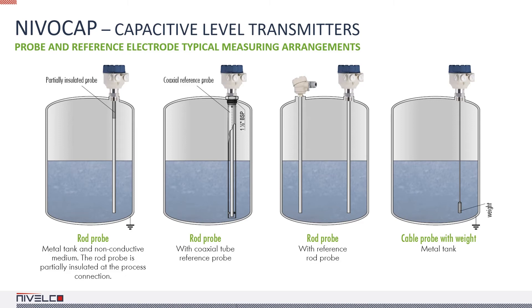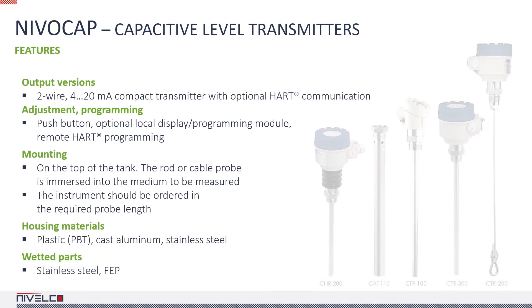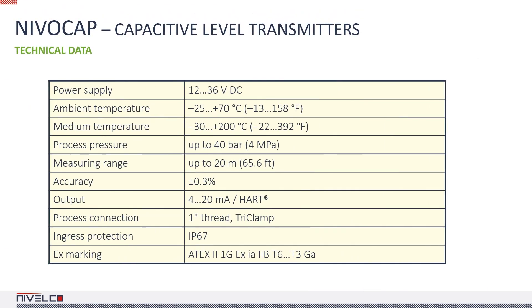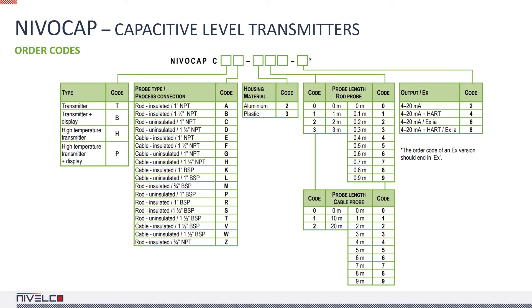The high temperature and EX certified models are suitable for hazardous environments and power generation applications. The probes of capacitive transmitters cannot be shortened afterwards, because the FEP coating must be intact for the device to function correctly. It's important to note that these transmitters have the best reaction times, so they are often used in applications where the level changes quickly. The loop current can be measured with a multimeter on these devices as well. NIVELCO also manufactures transmitters with a partially coated probe, but they can only be used with certain sufficiently clean, non-conductive media. These days we mostly recommend fully coated probes for such media as well.